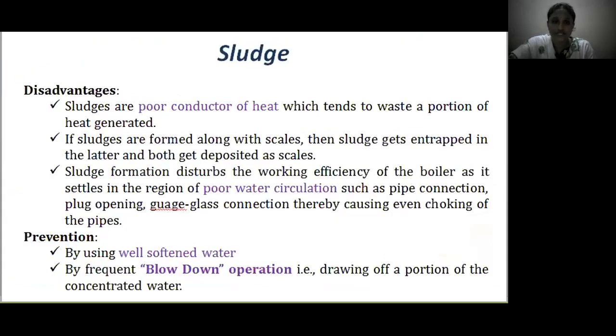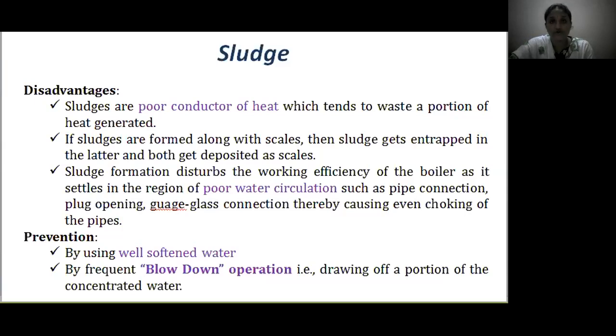What are the disadvantages of sludges? They are poor conductors of heat, which tends to waste a portion of heat generated in the boiler. If sludges form along with scales, they get entrapped in the scale deposits. Sludge formation also disturbs the working efficiency of the boiler by obstructing water circulation, causing choking of pipes. Sludges can be prevented by using well-softened water and by the blow-down operation — that is, withdrawing a portion of concentrated water and replacing it with fresh water.